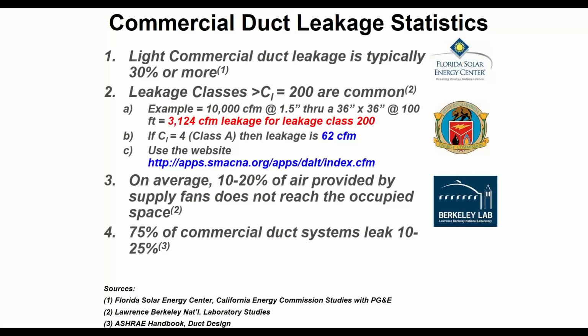So what we're recommending is that you look for Class A, which is currently a code requirement, but old buildings obviously are what they are. A new building, it's Class A. That's a class leakage of 4, which is only 62 CFM on that 10,000 CFM air handler. So it's a pretty ginormous difference. Obviously, on new construction, if you follow the codes, you will have a pretty good duct system. But there's a lot of existing buildings out there that are just built the way they were built, 10 years ago, 50 years ago, whatever it was. So we really want to focus on those buildings, the buildings that are already out there doing their thing and doing it poorly.